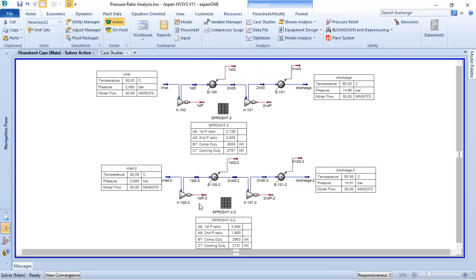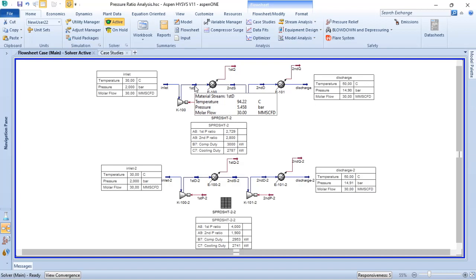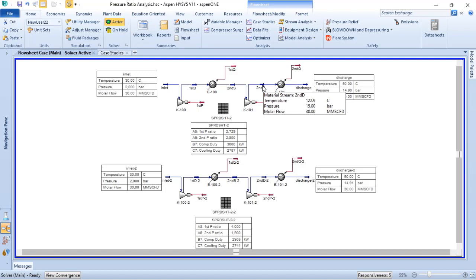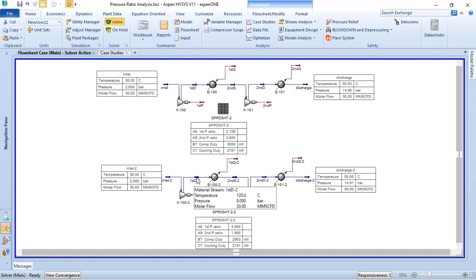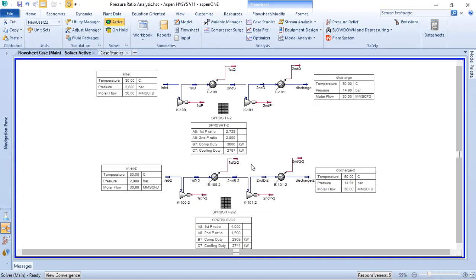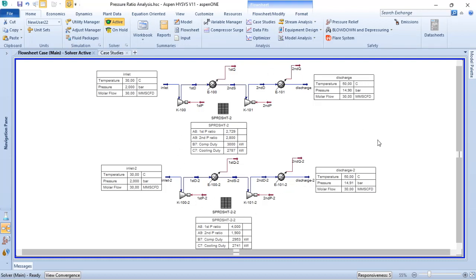When I add the optimized case to the process simulation, you can verify that in terms of discharge temperature we are still within the limit. In the standard case the first-stage discharge is around 94°C, while in the optimized case the discharge temperature of the second stage increases but all temperatures remain in a safe range.